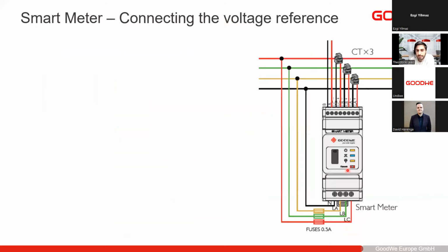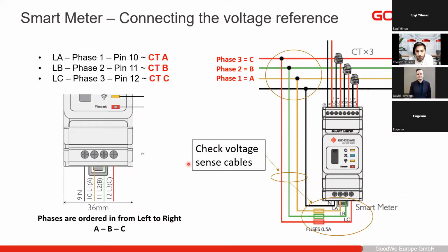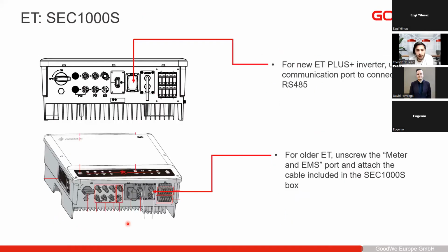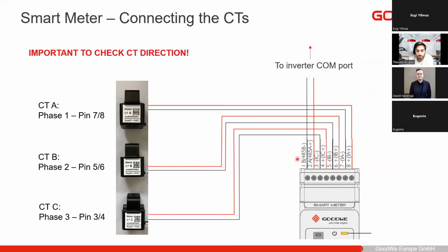But the difference is that on the bottom side of it, the phases are reversed. So here you don't have the first phase on the right, but rather you have the first phase here just after the neutral. So make sure, this is also marked on the smart meter, so just double check that you connect the correct phase. The phase of this one here should then also be connected to the correct phase of the voltage here. It's also recommended to have some fuses here of 0.5 amps between the voltage to the grid and the meter. Yes, so check the voltage sense. Here you see how they're ordered from left to right, and on the top they were ordered from right to left.